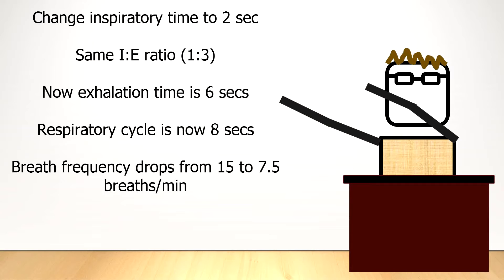If you want to increase the inspiratory time up to 2 seconds, but don't change the IE ratio, then the TI becomes 2 seconds, and the TE, or exhalation time, becomes 6 seconds, in order to maintain the IE ratio of 1 to 3.